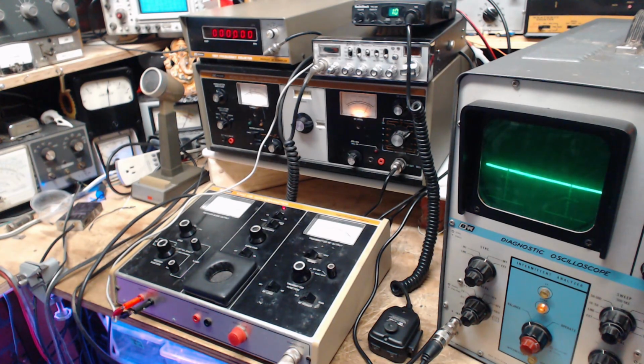So we're going to go up to the calibration. I'm going to read through these quickly. Model 1040 has been precisely calibrated at the factory for optimum performance and should not require readjustment unless a defective component has been replaced and it is absolutely certain that the unit will need to be calibrated. Well, when you go this far down the road, so many years have gone by, and with the indications we've gotten, I think going through the calibration process is worthwhile at this point, even if I don't change a part. Remove a couple of screws.